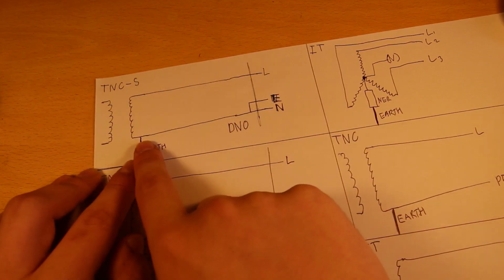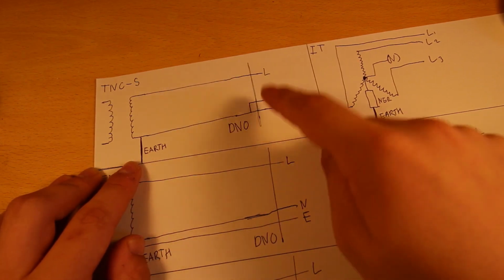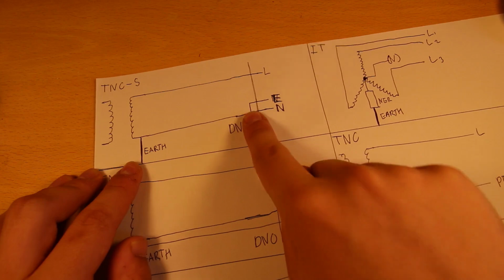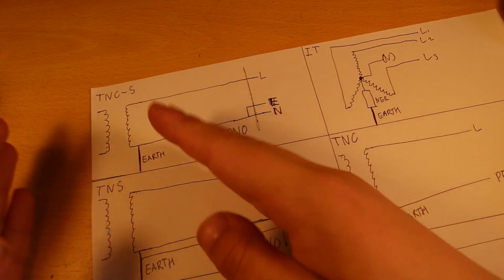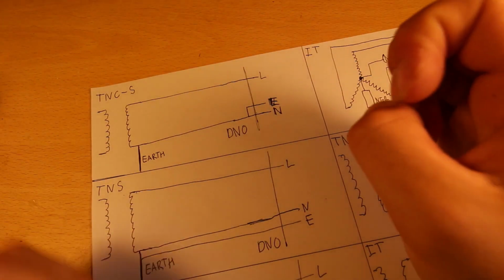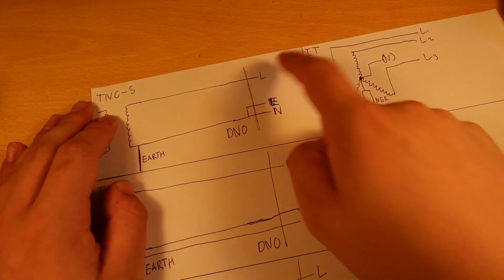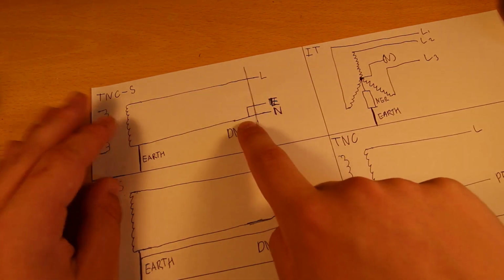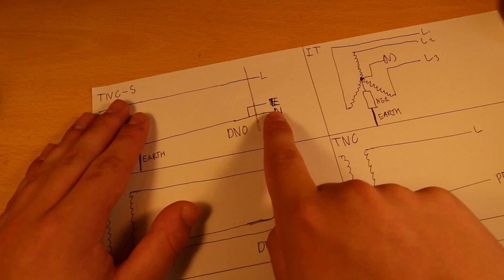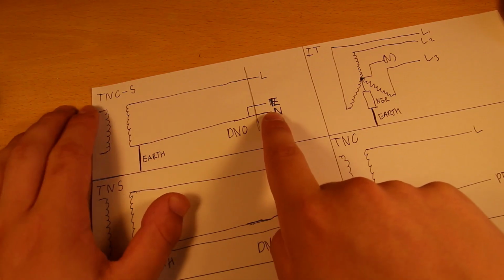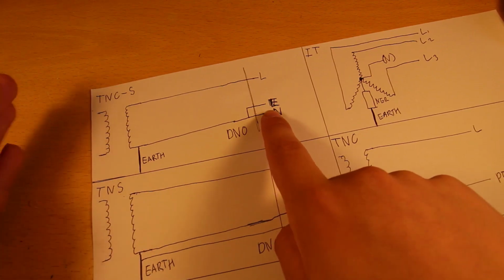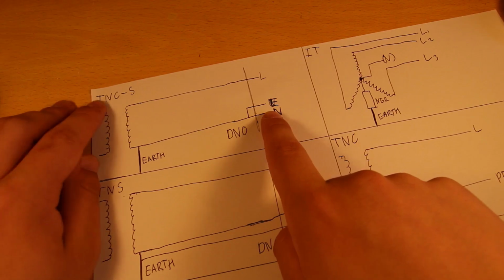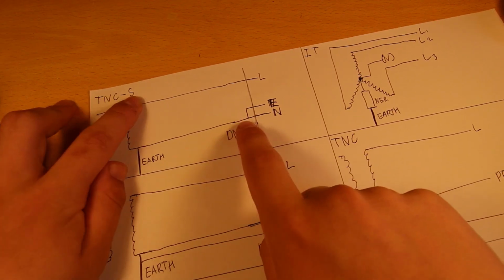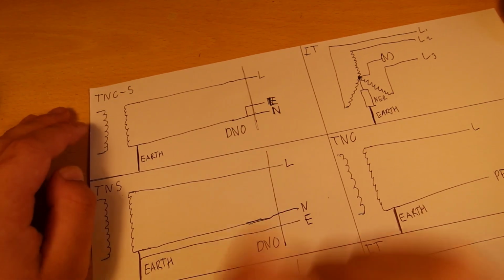There is then a conductor which comes out here, which is called the PEN, up to that point where the earth splits off, which is protective earth neutral combined, and the live comes out here. So we take the PEN up in the service head, we split the earth off out of it, and then we have a neutral, which is why we have TN-C-S. T stands for terra, which is earth. So earth, neutral, connected here, and then separated at the load.